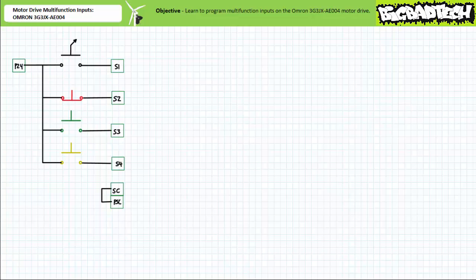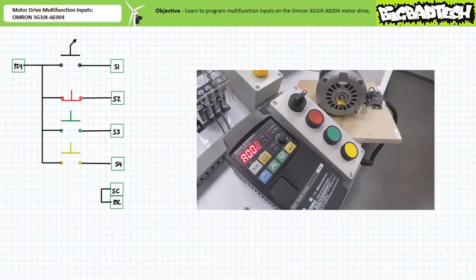Now we need to program this drive to recognize these four inputs. Warning — what I'm about to do now is dangerously wrong. Namely, I'm about to leap before I look. Let what is about to happen be a lesson to those that act before they think. Navigate to extended function parameter A002, run command selection. Select mode.